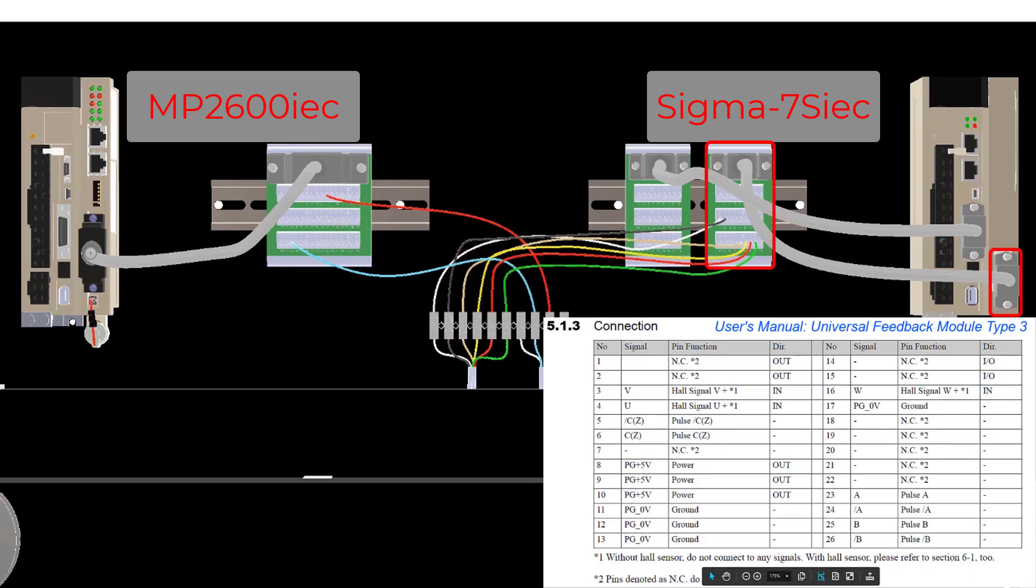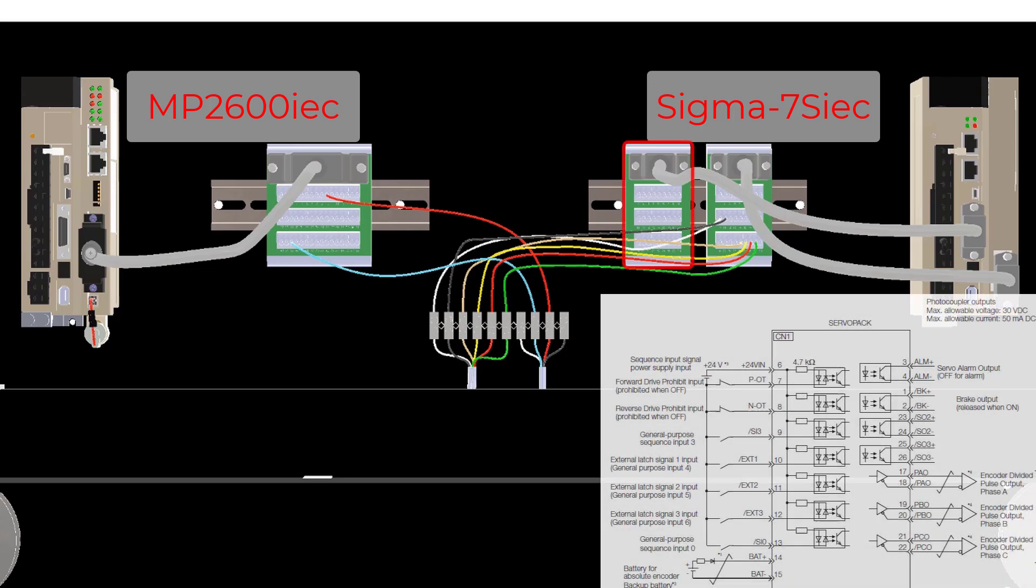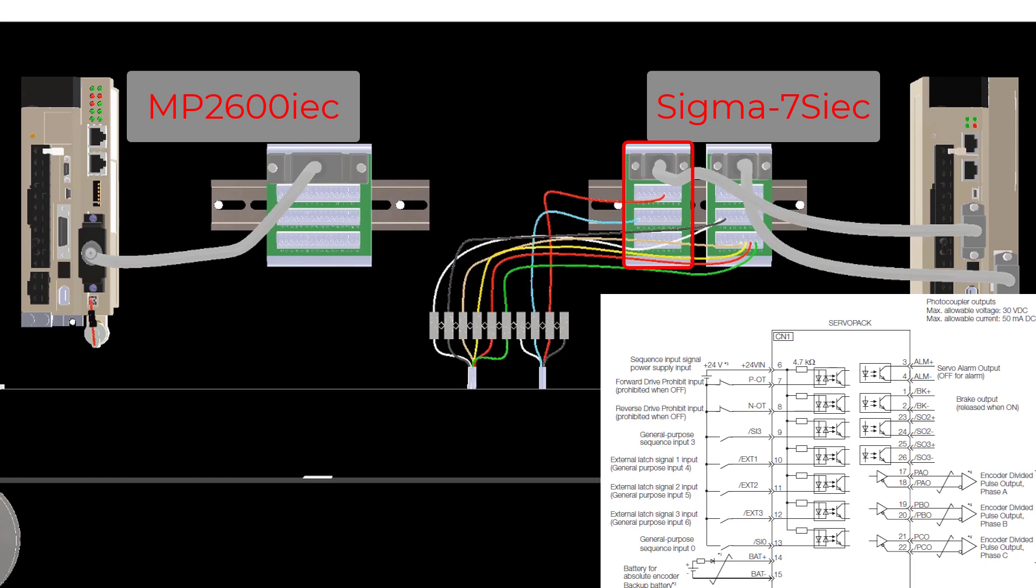The encoder wiring needs to go into the feedback option card. The feedback option card provides 5 volts for encoder power, so an external encoder power supply is not required. Any digital inputs and outputs along with the encoder latch input needs to be moved over to the Sigma-7 I/O on the Sigma-7S IEC.